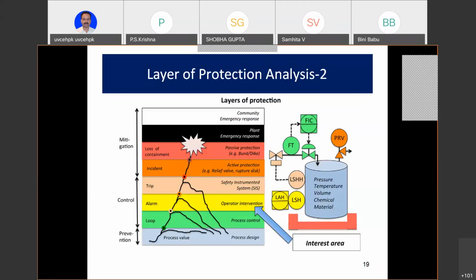Now, this is another diagram which, for you people, is not a very big deal. The only thing, it's more picturesque. And the brown one means it does not belong to you. It belongs to the other people. They're mechanical, chemical people. They put a relief valve. In this case, the FIC belongs to you. The green is yours. And then the pink is all emergency level switch going on to a valve. And this is a level switch, the alarm level. And then next is your trip level, pink. This is your shutdown.